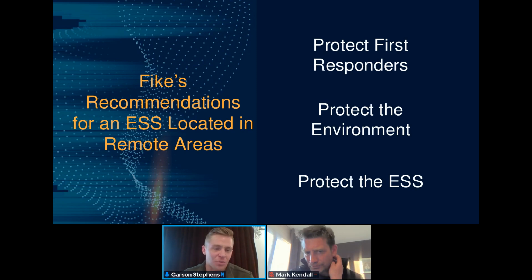Everybody knows there have been a lot of videos on YouTube and online about that event out in Arizona at a solar farm, where a BESS had an explosive atmosphere that was unmitigated. This was a long time ago, before people understood what the risk was. They opened up the door, introduced oxygen into it, had the right mix of fuel, oxygen and ignition, and it hurt people. The idea is we never want to do that ever again, and so that's our number one priority.